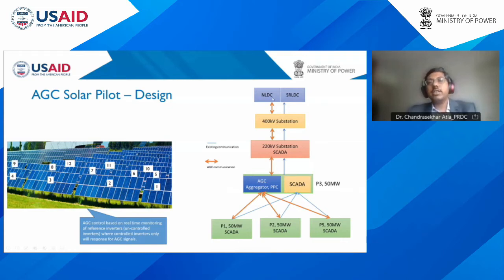At NLDC, they can control this complete plant as a single virtual plant, like a 250 megawatt block, or NLDC can also give individual block-wise signals in specific conditions. Now, when it comes to the control, the adopted philosophy is on the left side, if you can see it. It is very critical for any AGC implementation, especially for renewable energy sources, where you cannot schedule accurately because you cannot forecast with that much accuracy. You can do the forecast, but maybe a 10-15% error will always be there.